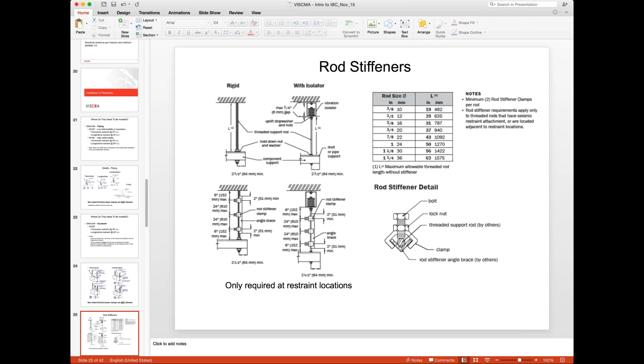Now, where do they need to be installed? They being seismic anchorage and such. Right now we've been talking mainly about overhead suspended equipment, but the same process of going through the calculations, going through the requirements, going through the seismic design category determines what needs to be anchored. Then once you've determined that this equipment is floor mounted and needs to be anchored, you have to go through the calculation to determine the load on each anchor, and then use the appropriately rated anchors.